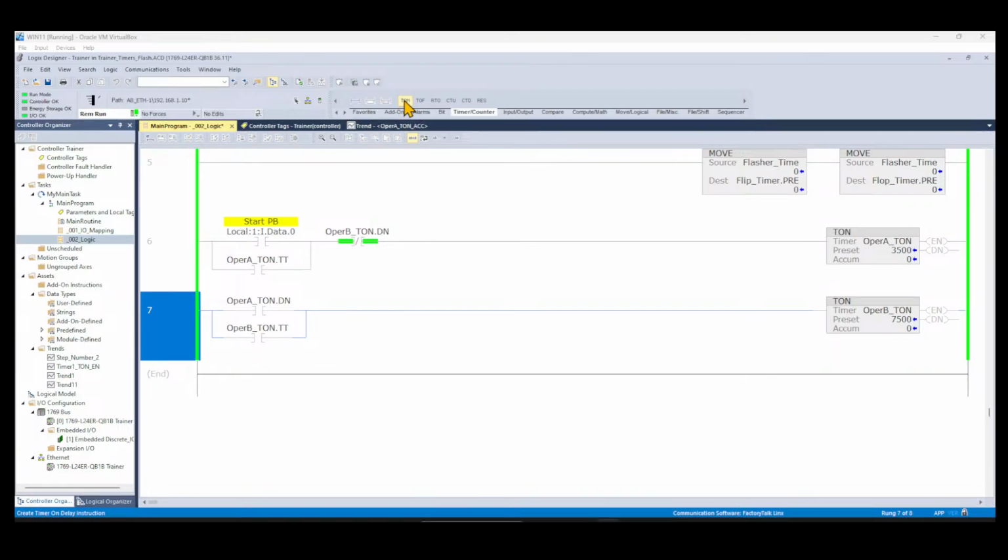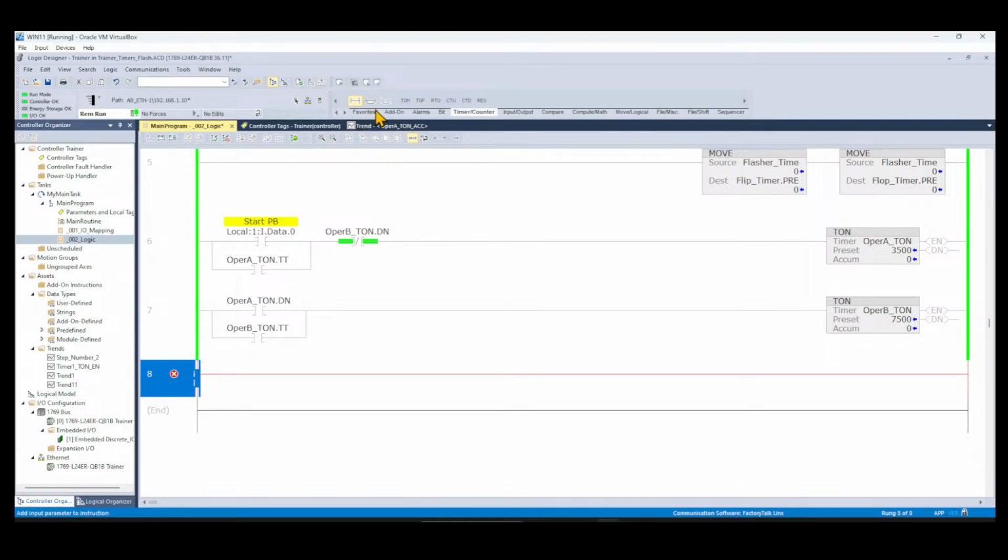So again, we'll go through timers. They are useful in developing logic, and we use timers as debounce timers. Say you have a sensor and you want to make sure the signal from the sensor is settled before you call it an object being blocked on the photo eye, we just use a debounce timer to ensure the signal is on.